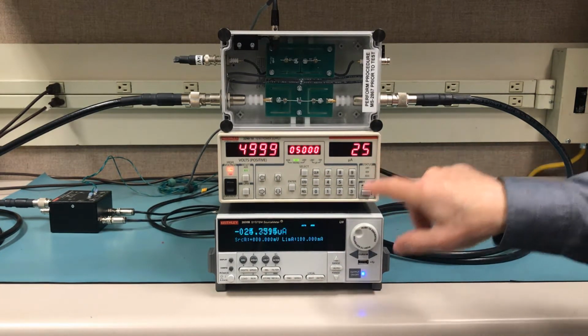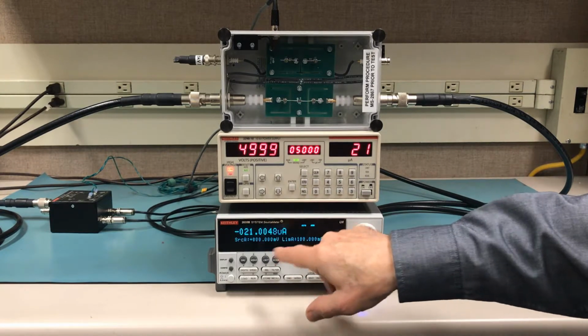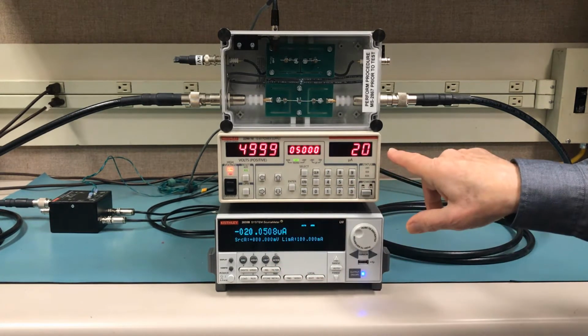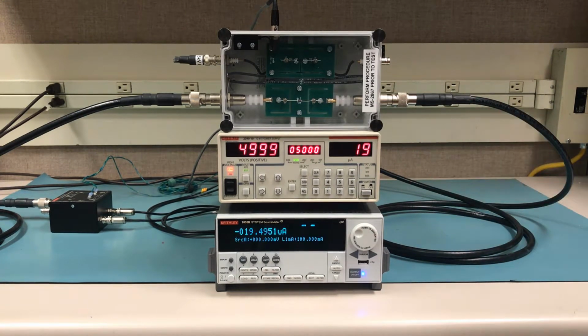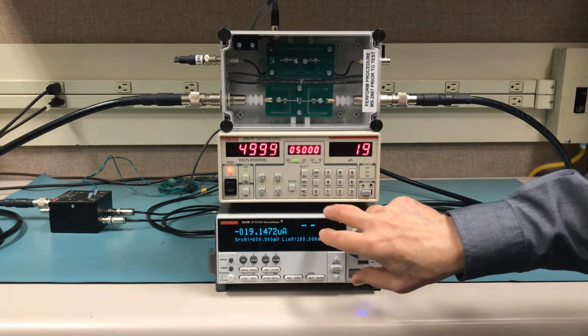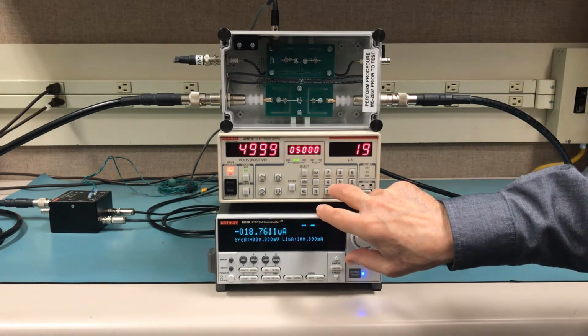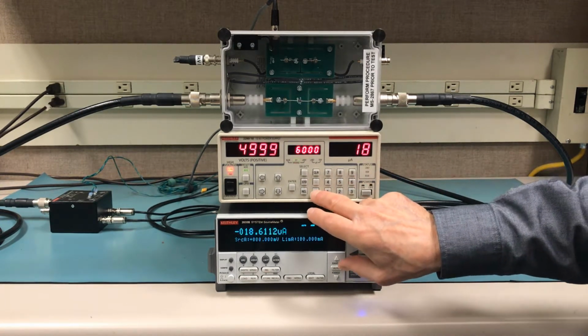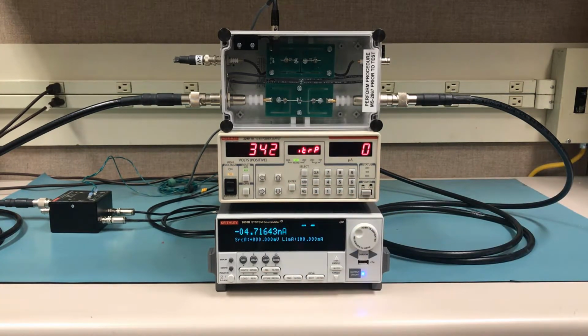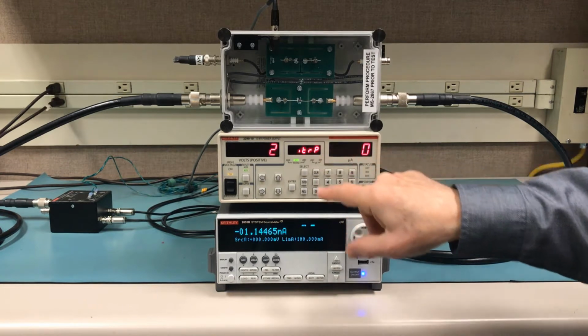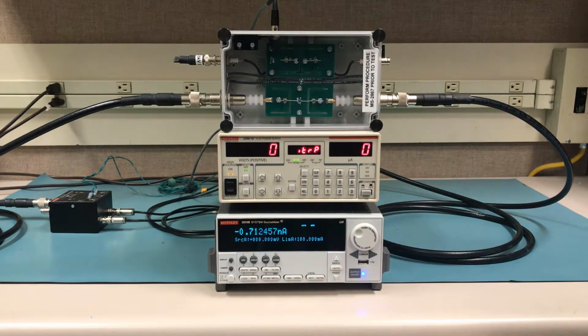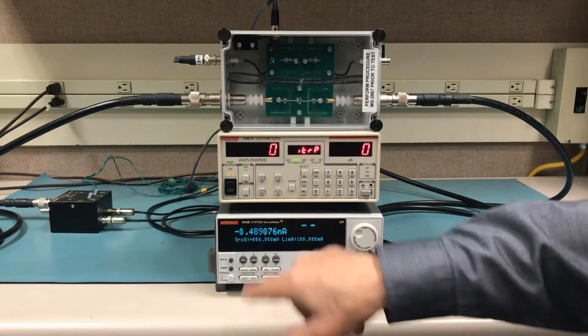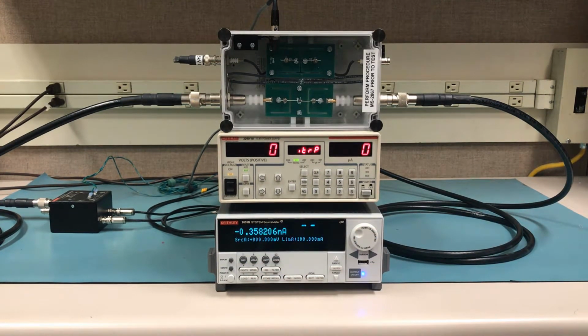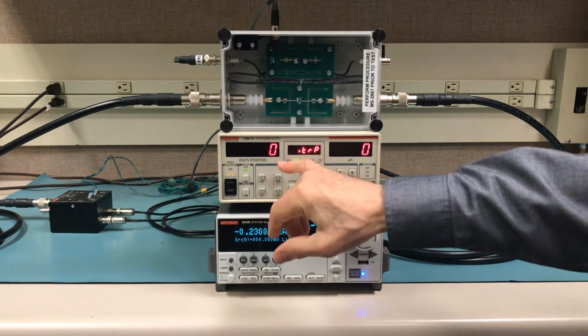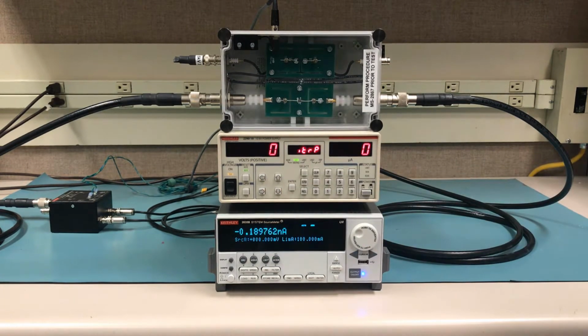And now you're seeing that we're getting near breakdown as we're starting to increase the current, and you can now see that the power supply itself can measure the microamp current level. But we haven't broken down the diode yet, so let's go to 6,000 volts. Up, and that does it. We've got the trip condition. We've exceeded the 1 milliamp limit, and our protection module is protecting our source meter from that breakdown of the diode, and the power supply safely went to 0 volts during that period.